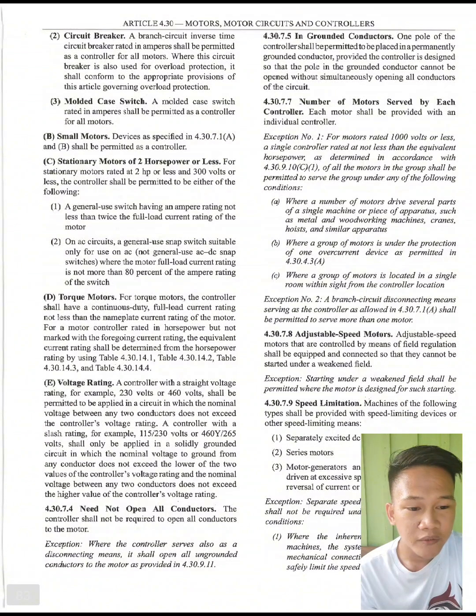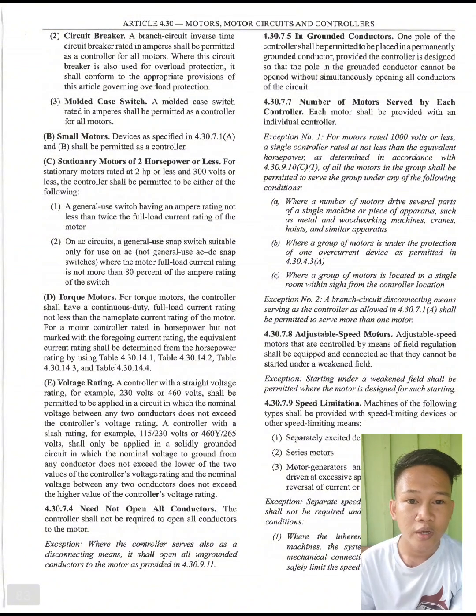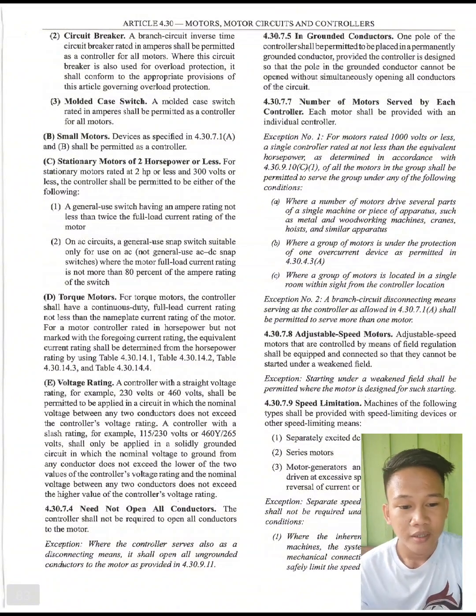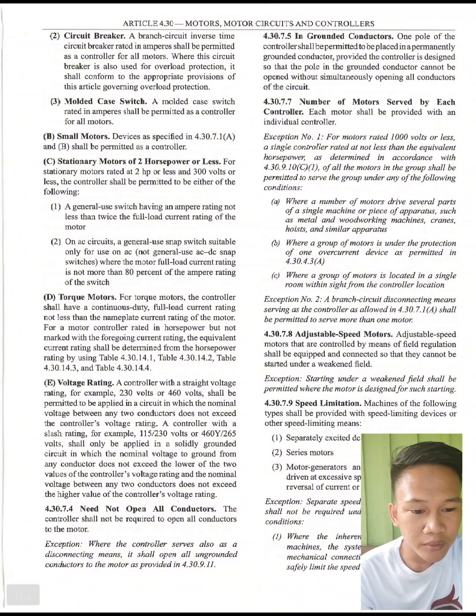So, exception. Separate speed limiting devices or means shall not be required under either of the following conditions. First, where the inherent characteristics of the machines, the systems or the load, and the mechanical connections thereto are such as to safely limit the speed. Second, where the machine is always under the manual control of a qualified operator. So, the qualified operator.